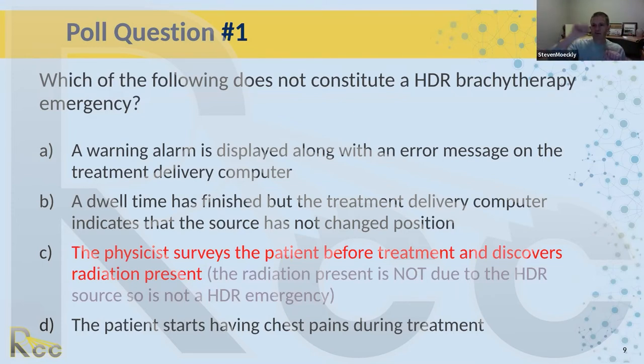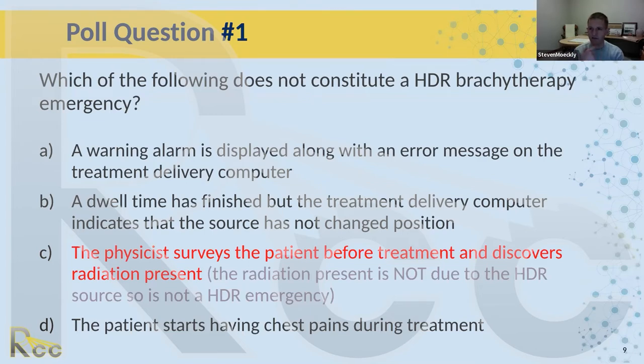The physicist surveying the patient before treatment and finding radiation present is not an HDR brachytherapy emergency. Before the patient enters the room, you should survey the room to confirm no radiation is present. You then survey the patient because they may have had a nuclear medicine procedure. You need that baseline so you don't get to the end of treatment and wonder whether radiation present is from the source or from a prior nuclear medicine procedure.